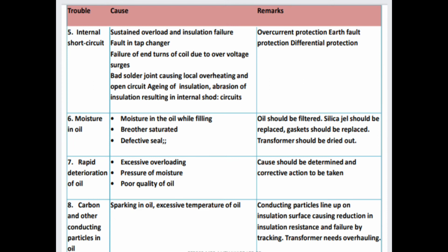So fifth is internal short circuit. Causes: sustained overload and insulation failure, fault in tap changer, failure of end turns of coil due to overvoltage surge, bad soldered joints causing local overheating, and open circuit, aging of insulation, deterioration of insulation resulting in internal short circuit. Remarks are overcurrent protection, earth fault protection, differential protection. So these are the remedies.